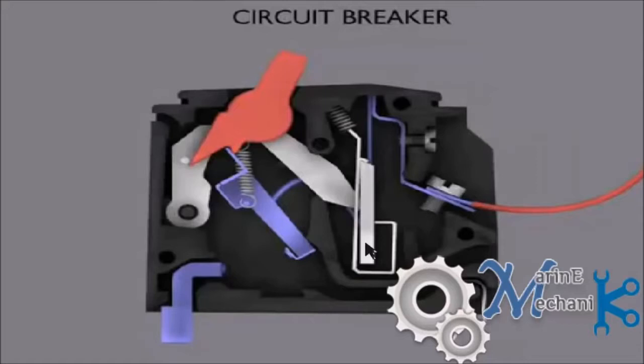So after the bimetallic strip cools down and comes back to its original position, you will be able to reset the circuit breaker from the trip position. As I said earlier, the on position is towards like this, which I have shown with the arrow mark. Off position is this, and the center position will be the tripped condition.